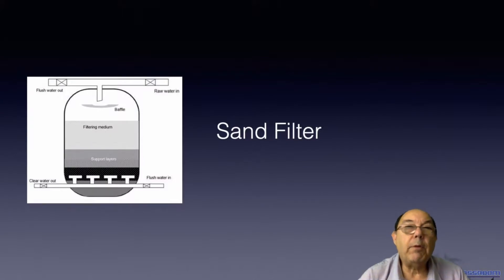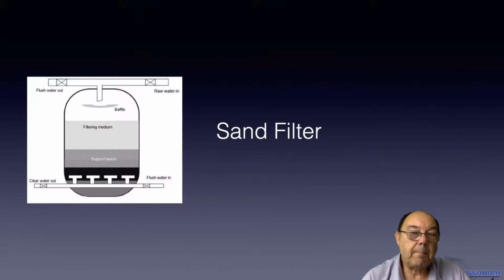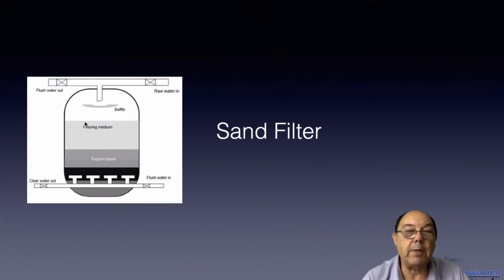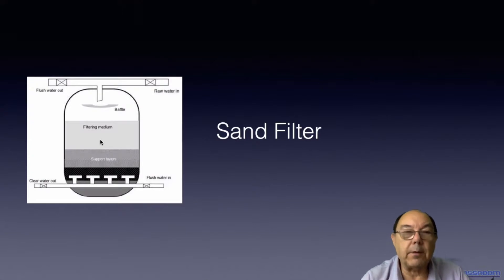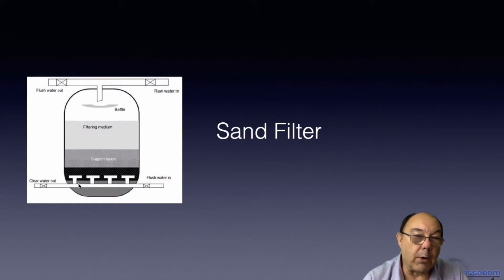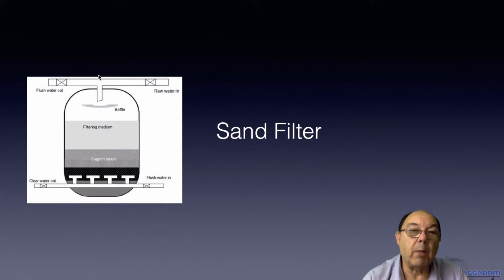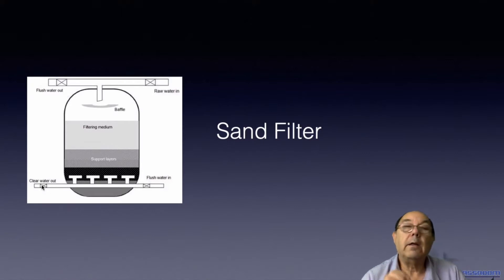Once you've been through the settling regime, there will be really fine particles that you would never settle out, and therefore it's very common to have a sand filter. With a sand filter we have large rocks, smaller rocks, and eventually sand. The raw water comes in carrying these tiny particles — this spreader is just to spread the water out so you don't dig a big hole — and as the water permeates through the sand, the small particles get trapped between the sand particles, giving you clear water coming out. Eventually the channels between the sand become filled and the flow rate goes slower and slower until the rate is unacceptable.